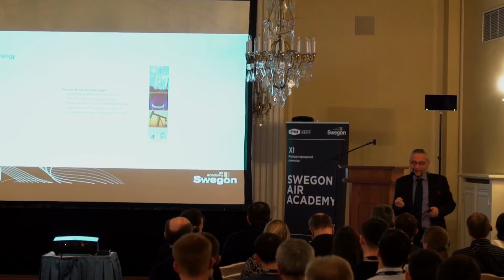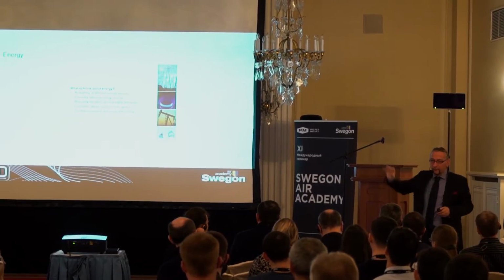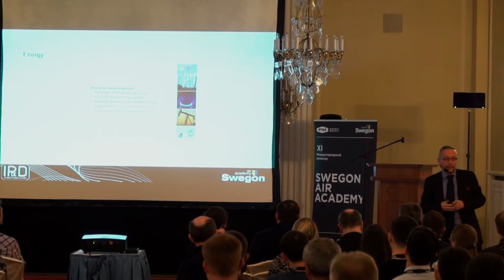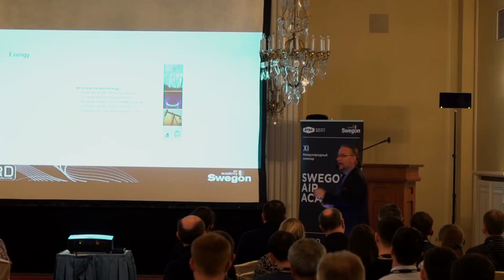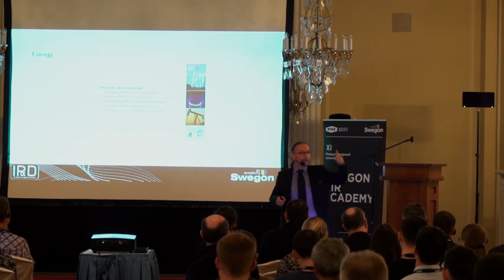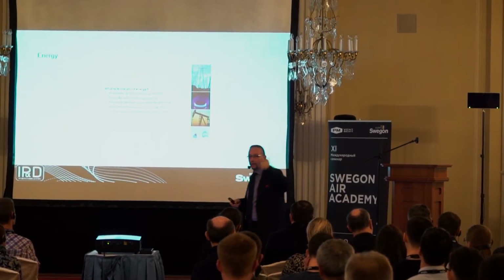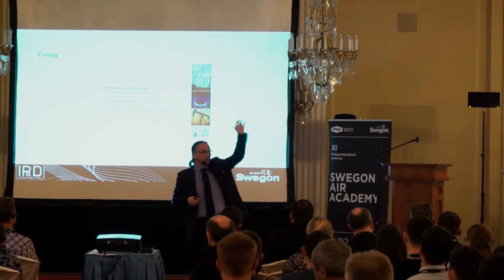So you actually buy 100 kilowatts of district heating from the city and put it into one part of the building. At the same time, you buy a chiller on the roof producing 100 kilowatts of cooling, putting that to the south. That chiller, to produce 100 kilowatts of cooling, will actually have a compressor and a cooler that sends out 130 kilowatts of heating on the roof into the air.